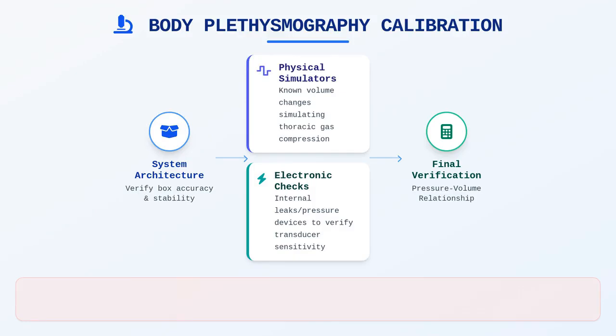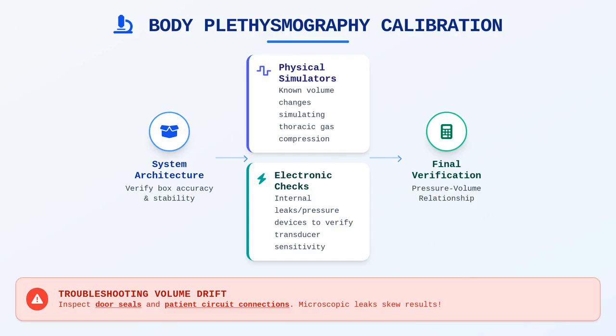We are essentially verifying the box's ability to calculate the thoracic gas volume by measuring the pressure-volume relationship during simulated efforts. If your volume measurements drift during these simulations, check for leaks in the door seals or patient circuit connections, as even a microscopic loss of pressure integrity will skew your plethysmographic results.